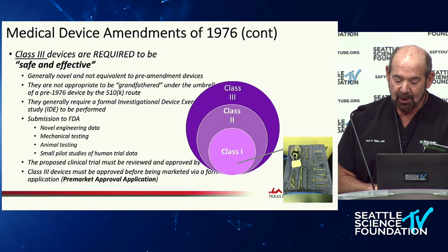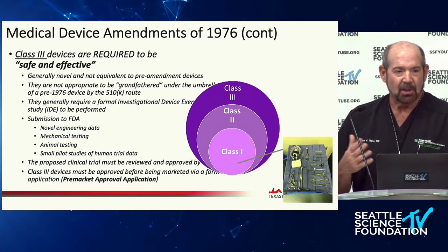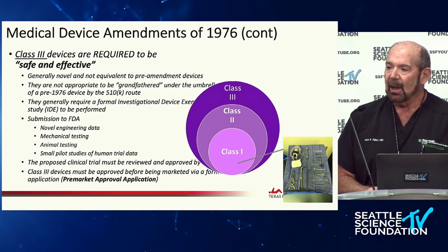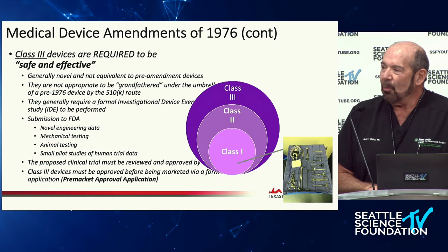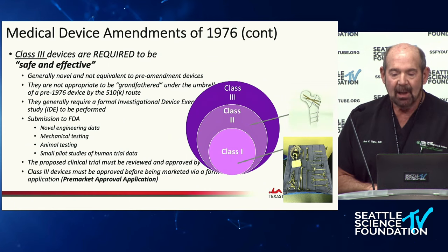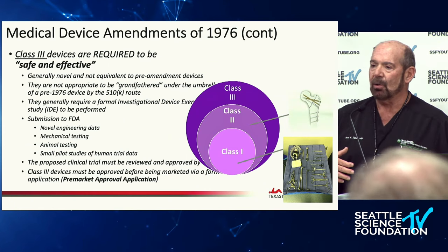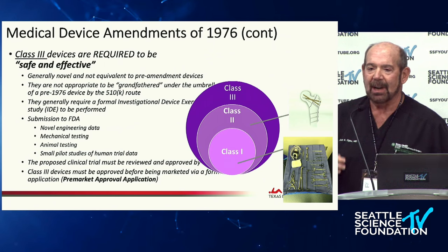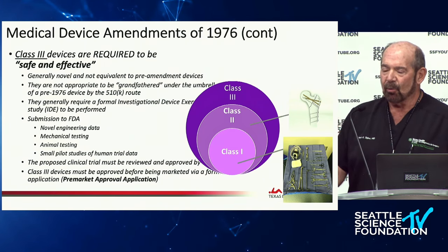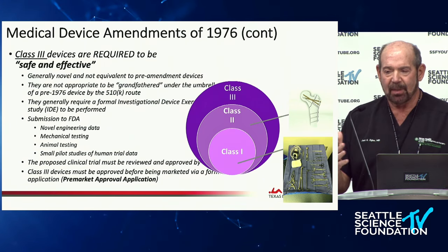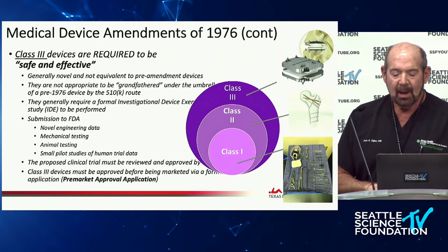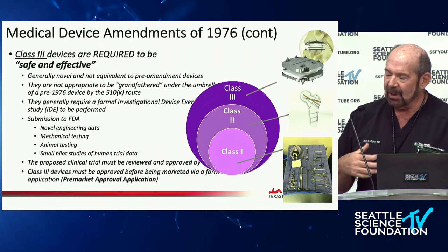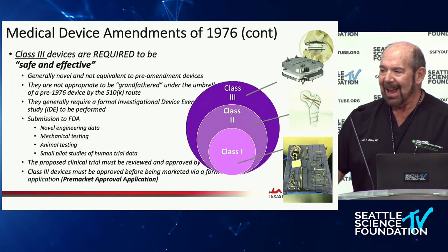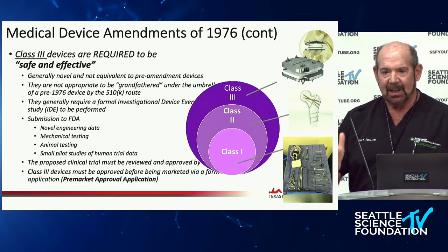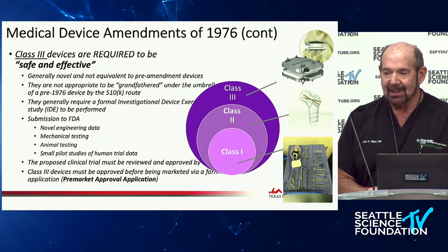So here are the three classes of devices. Class 1, as I said, are general purpose instruments, and again you just have to show you're making them appropriately to standards. Class 2 would be if you came up with a new hip fracture nail system, plate, or rod - something substantially equivalent to things that have been around before. But then you have novel technology, something that's never been used and has no device you can easily say is substantially equivalent pre-1976. That's what puts you into Class 3.